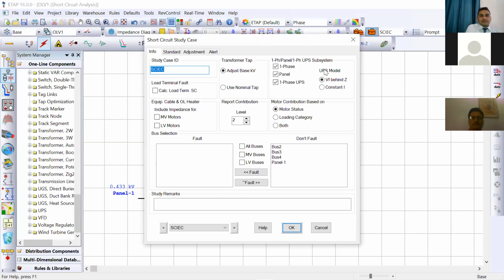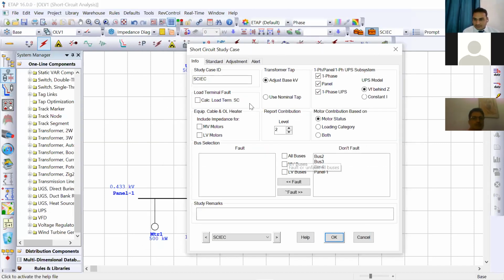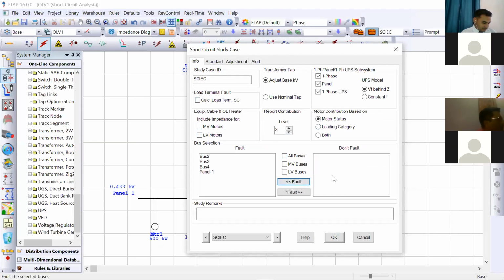Different configurations are there. Presently, MV motors we are not using. LV motors we are using, but with 1 motor only. So these all are default settings available. We presently do not want to disturb it. Only thing we have to do is this. All the buses in the network, we have to take it on the fault side. That means fault is created on each and every bus.